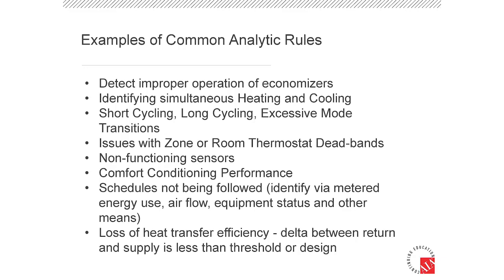That same customer with the 65 buildings, after they saw the value and got financial return from that quick, easy application of analytics, then they went further and applied it further into the building. And they had a major problem in a couple of new buildings. Hot summer day, people are screaming, but they had actually connected and started analytics. And what they found was, and this was really interesting because the guy related it to me, he says 25% of the zones in the building were absolutely miserably uncomfortable, and the other 75 were fine. To the point that I could be in my office and be perfectly comfortable, and 14 feet away, you were dying. How could this be?